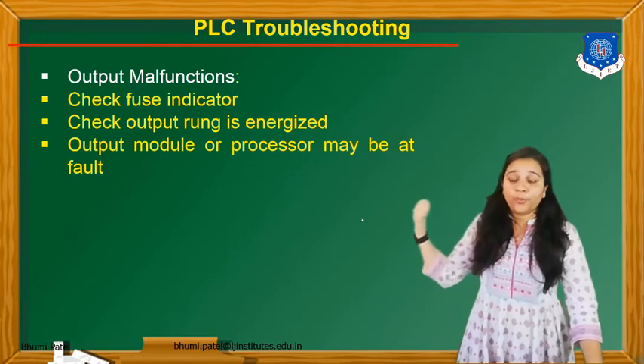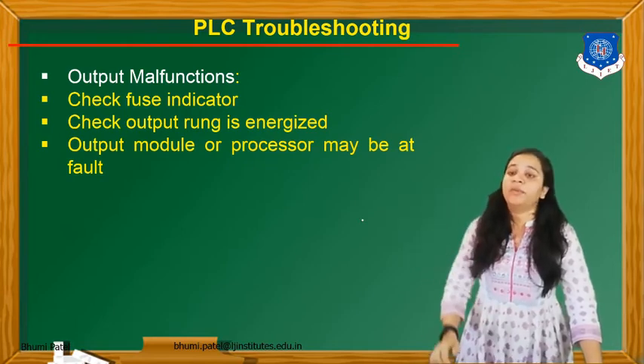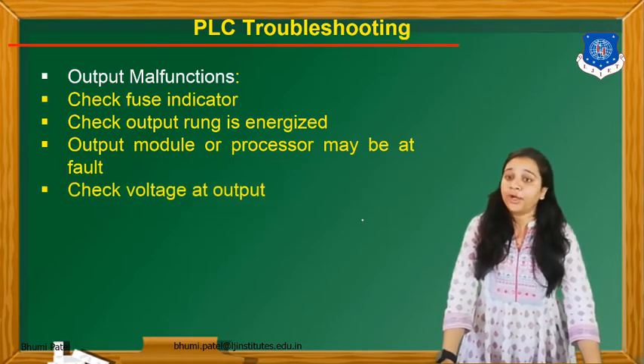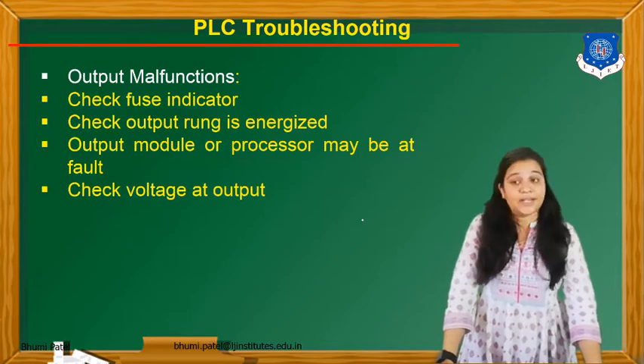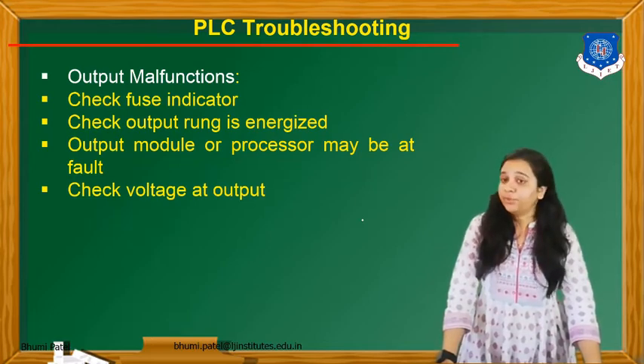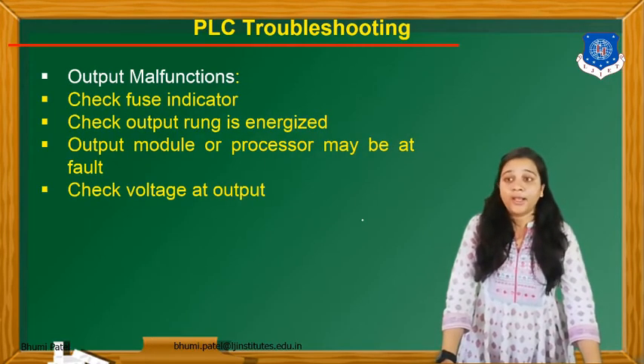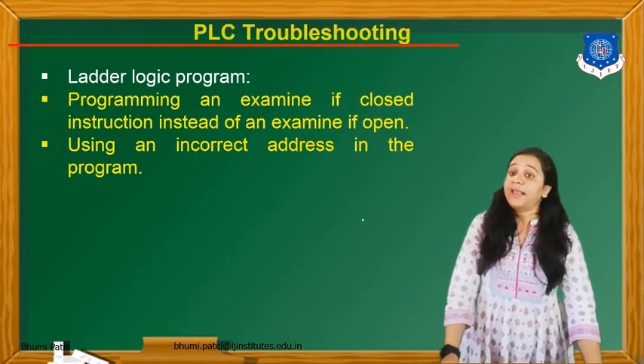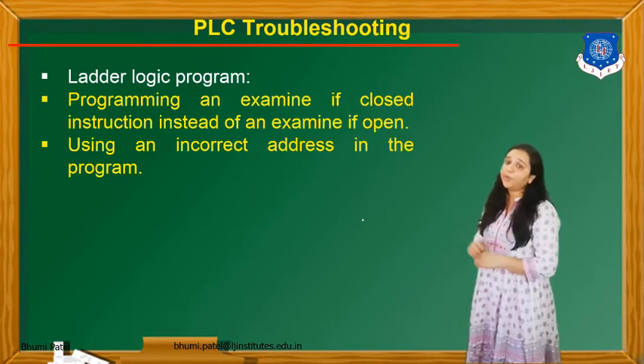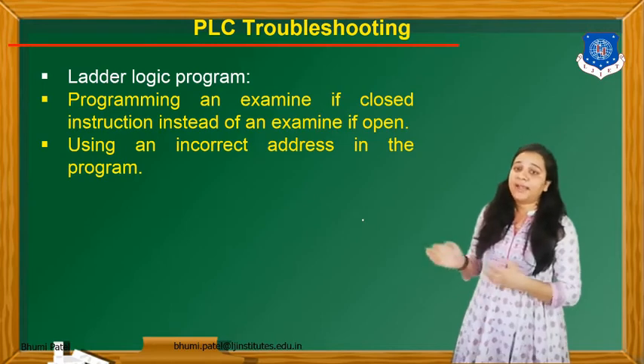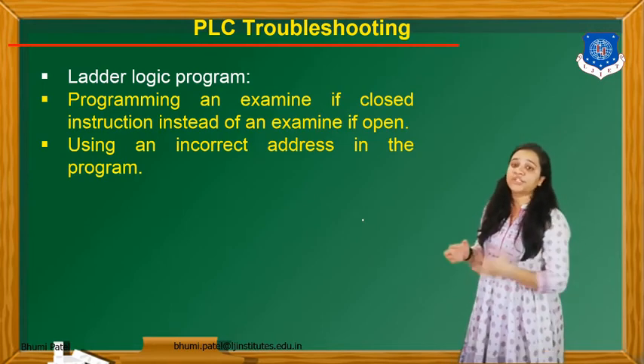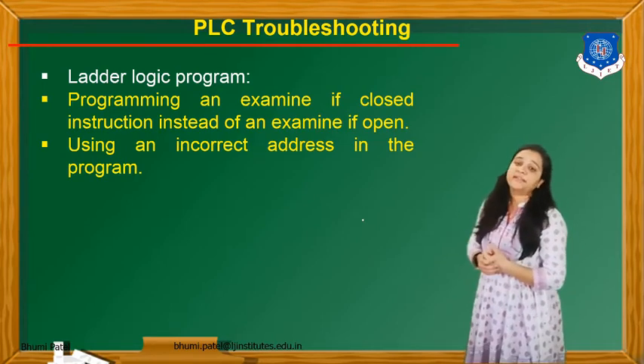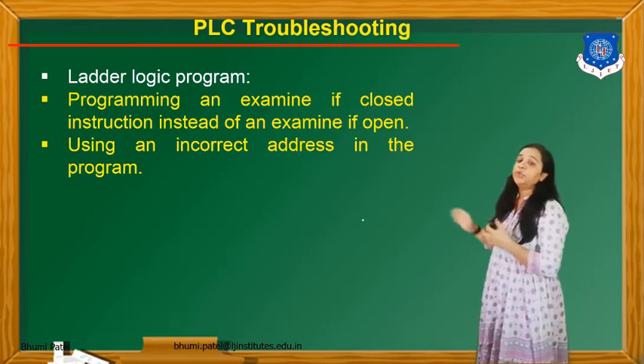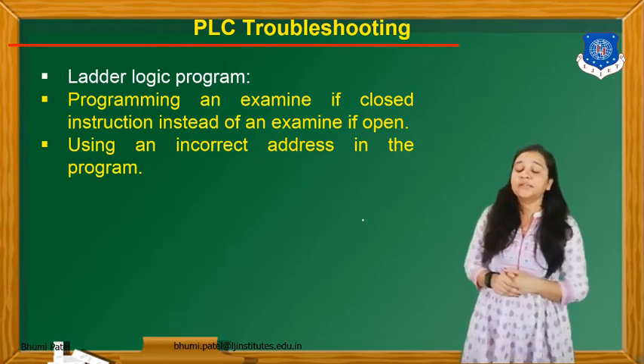Then we check whether the output module or the processor may be in a fault condition or not. We have to check the voltage at the output side as well as the input side. So this is all for the output malfunction. And the last one is the ladder logic program. Common errors are programming an examine if closed instruction instead of examine if open, and using an incorrect address in the program.